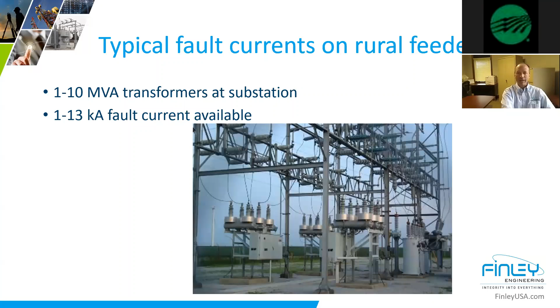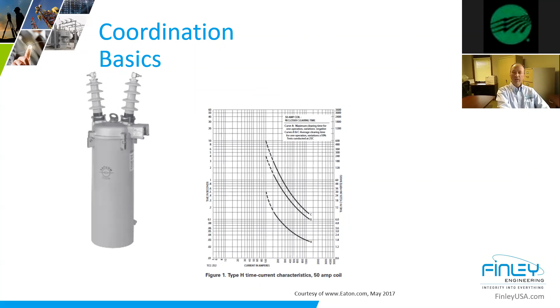You see it bounded by those ranges by that size of transformer. Those that have looked at a light table graph and tried to coordinate your typical hydraulics, you're fairly limited. You've got those ABC curves, and you can try to plot those against each other and see where things fall. And now with the advent of our smart breakers, being able to pick the curves, we can do a much better job of coordination.